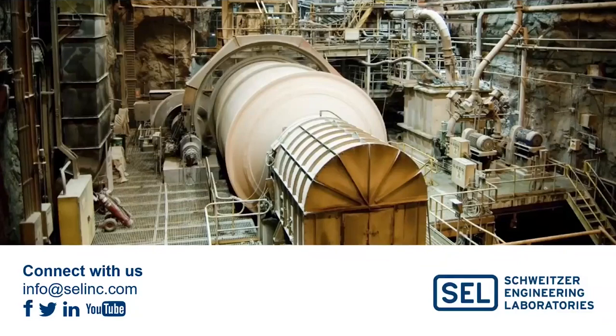All right, thank you. One question came up: can this 700BT be used in a 3-breaker main-tie-main auto transfer? We can use one 700BT relay if it's a 2-breaker system. For a 3-breaker main-tie-main system, we need two 700BTs. Yes, we can use that, but we need two relays. Thank you, Monica.